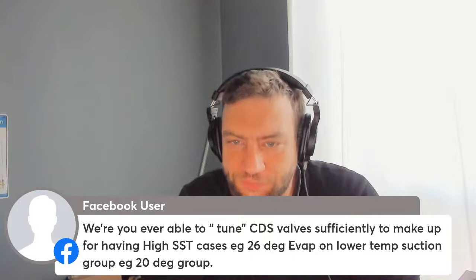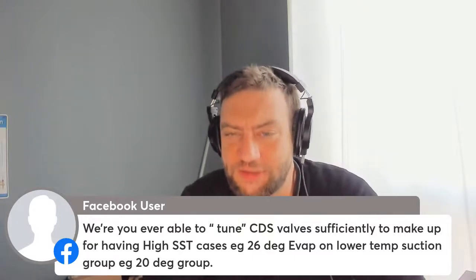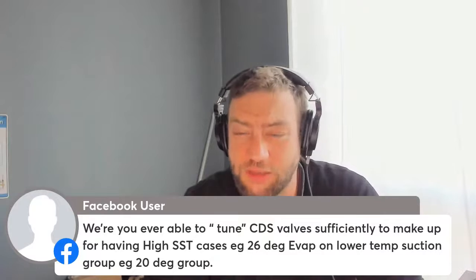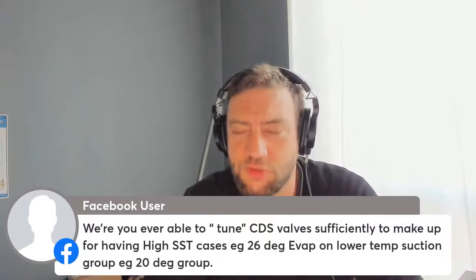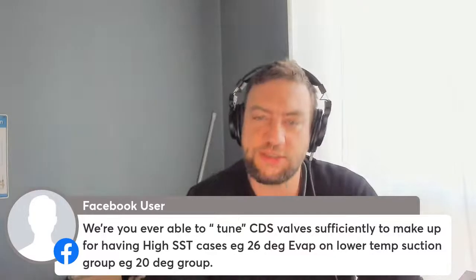I don't know what you mean by tuning. I guess to achieve a more accurate saturated, or not to go lower. Some of these stores, because they put these high efficiency cases in, a lot of times what they'll do is actually put the lowest SST case on the low temp header, so they can raise the suction pressure on the other header that they did the retrofit for. Right, because they have to raise the suction pressure. But if you have one case running at plus 16 or 18, and then all the rest running at plus 24, plus 26, it causes a lot of short cycling, a lot of EPRs to slam down. Yes, not to go lower.